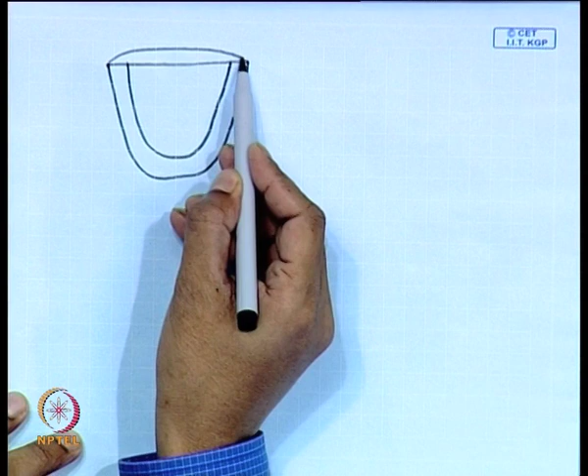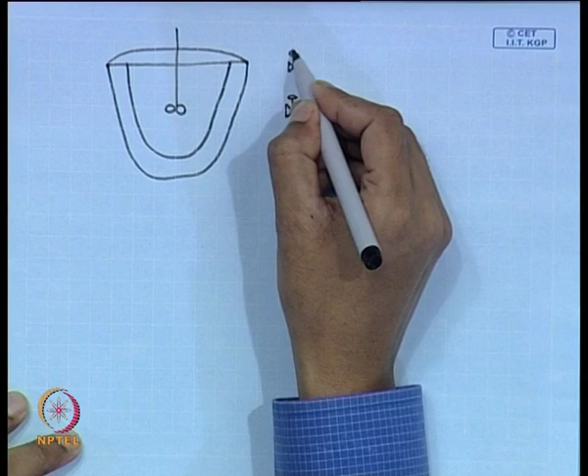Now, we will try to configure the split range control for this example system. This is a schematic of the non-isothermal batch reactor. This is a jacketed batch reactor. Fine. One valve is used for cooling medium and another valve is used for heating medium.